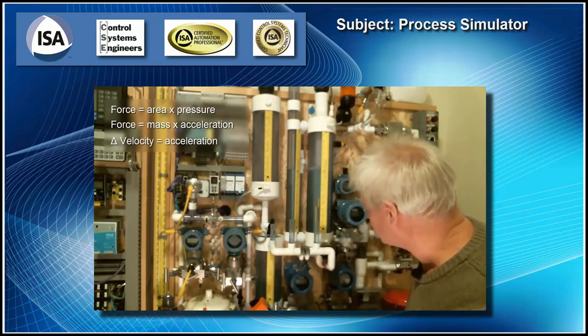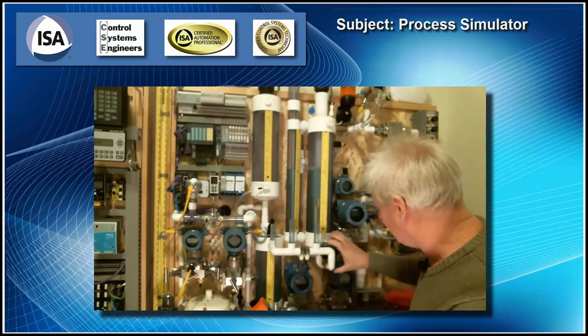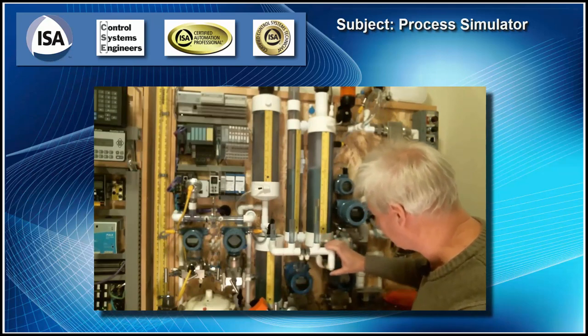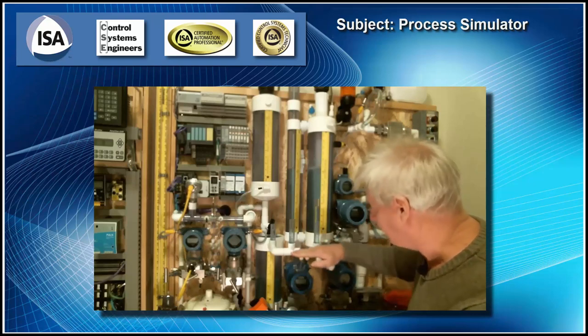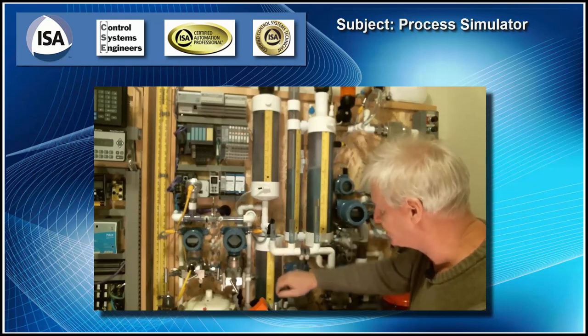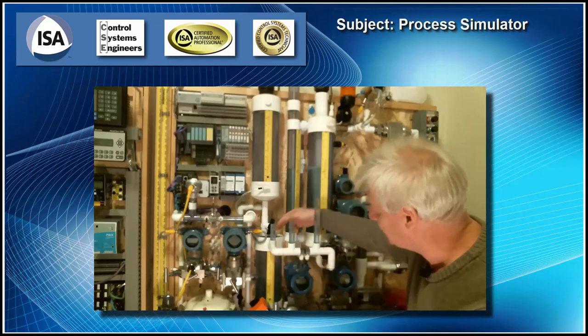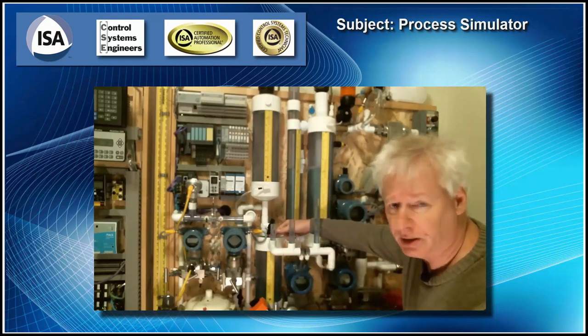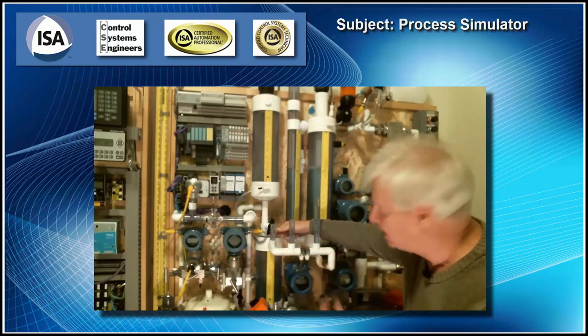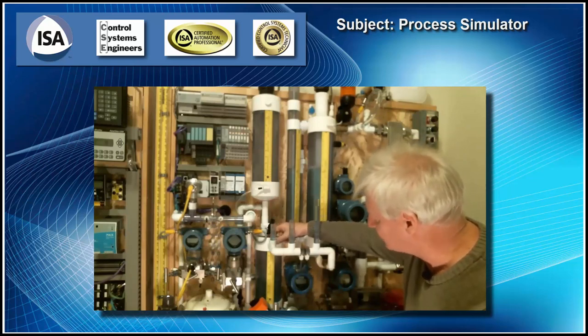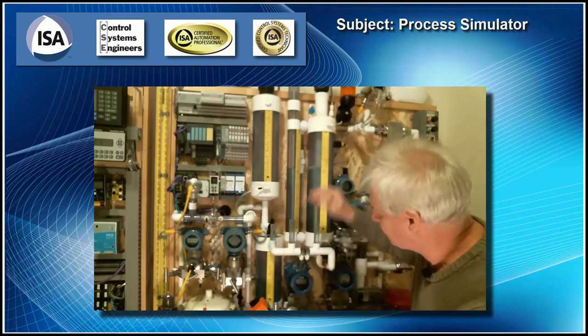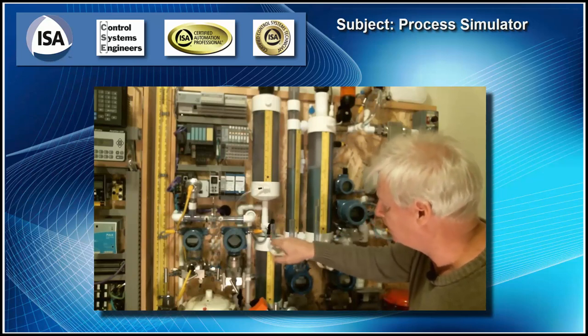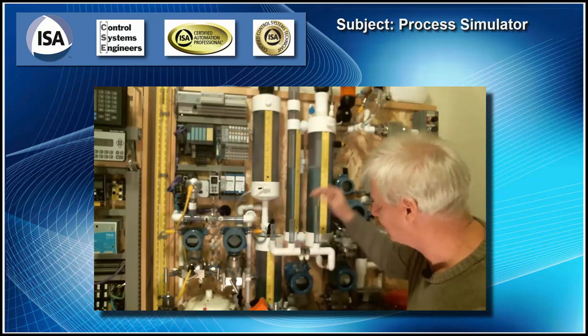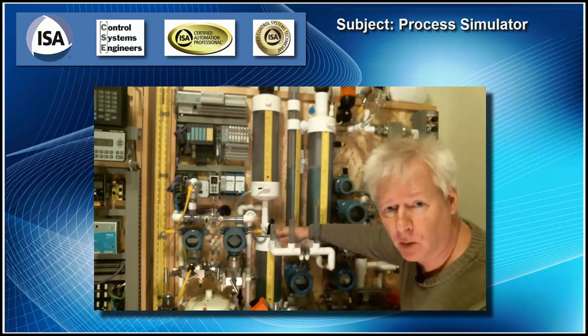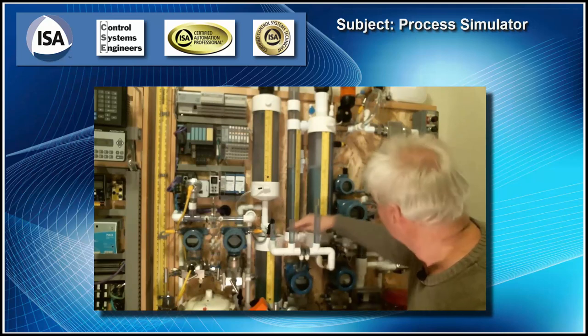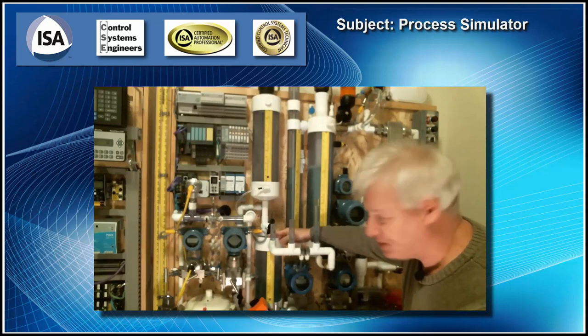This piping system is just like an electrical circuit. These are resistors. The valve's a resistor, the 90s are a resistor, the pipe is a resistor, and behind here, I actually have a little orifice. It's a small washer, and it has a hole in it, and this resistance acts like a long piece of pipe. That's why the water stands up here instead of being at zero going out, because we know at the end of our run, we have no energy left. We've used all of our energy, going from maximum energy to zero energy.